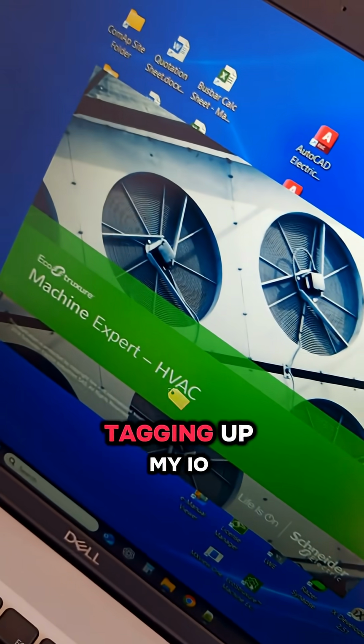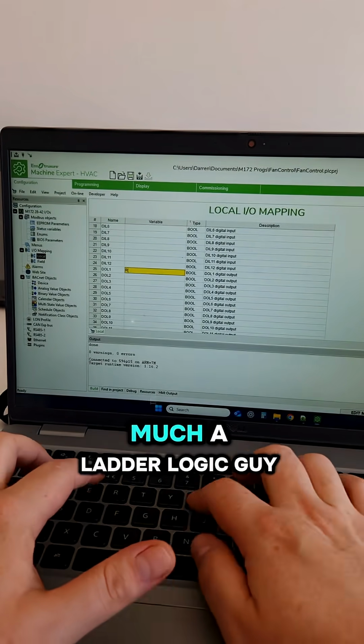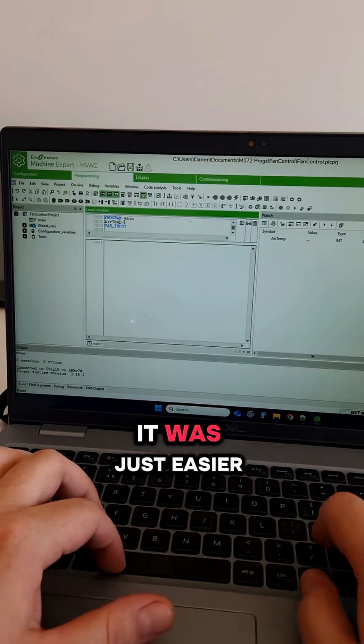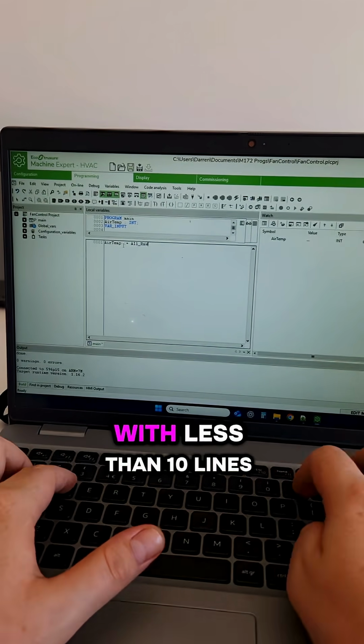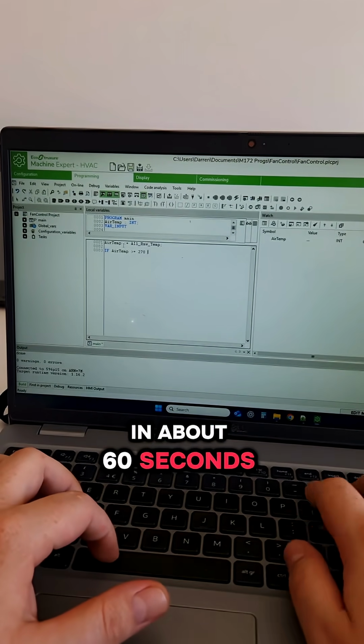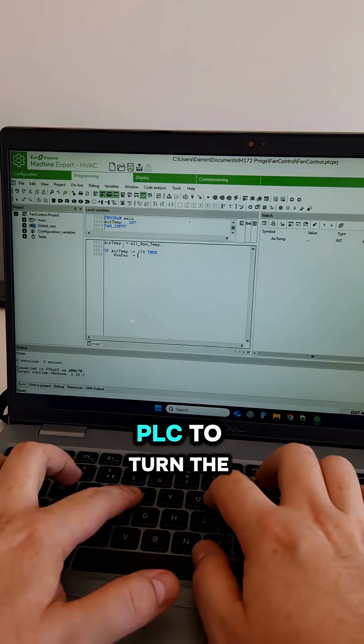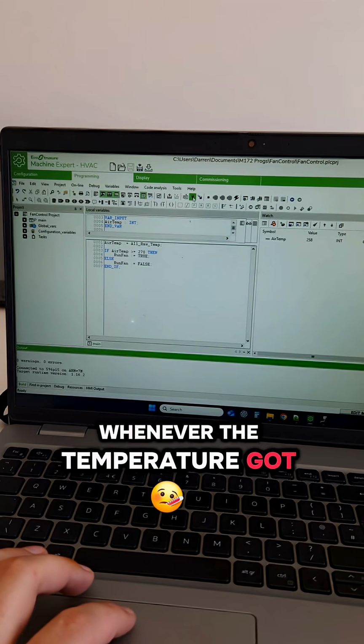Once the software booted up, it was a case of picking the correct PLC, tagging up my I/O, and putting a couple of lines in structured text. Normally I'm very much a ladder logic guy, but in this case it was just easier to go with structured text. With less than 10 lines of code and about 60 seconds programming time, I could get the PLC to turn the fan on whenever the temperature got above a certain set point.